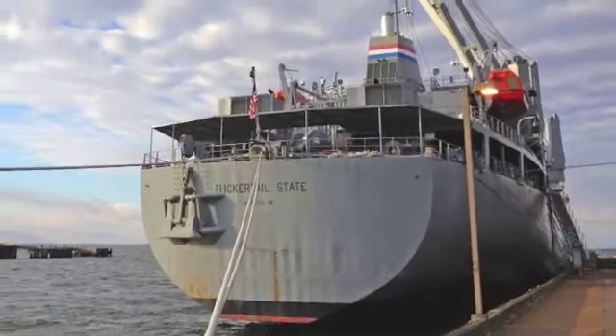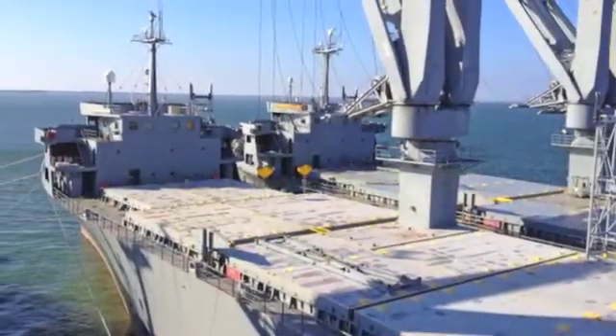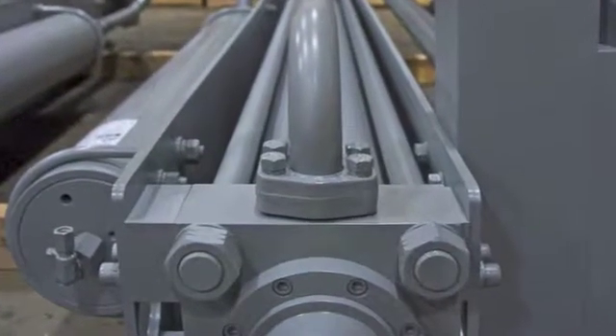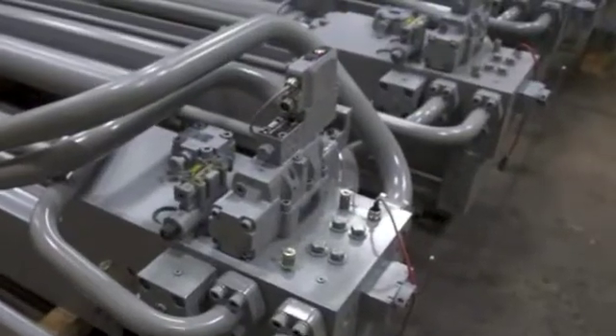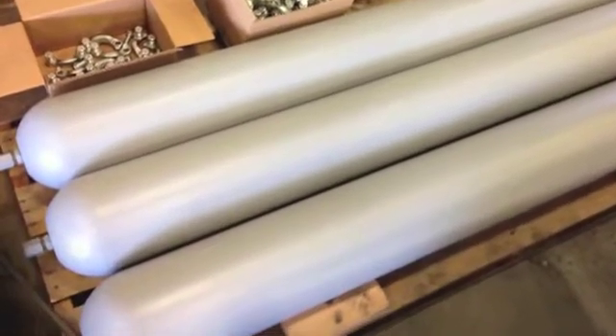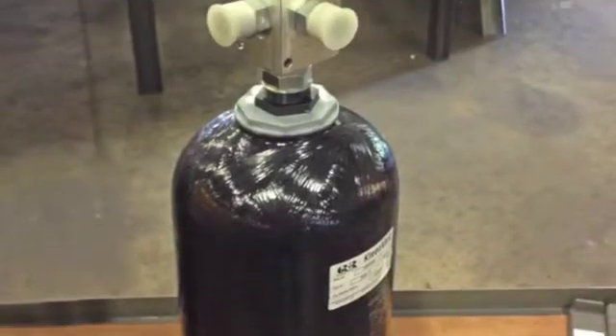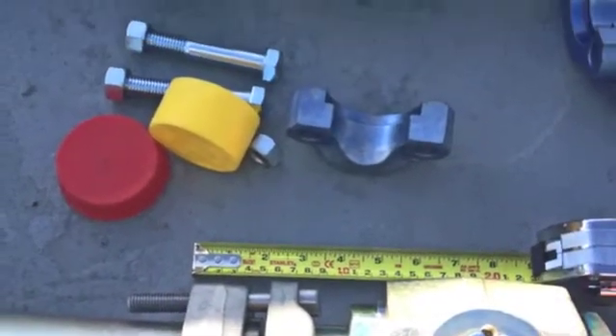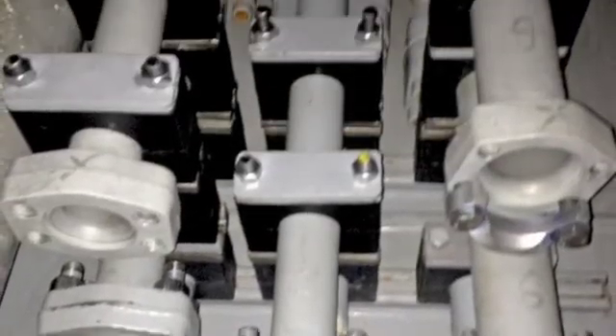Based on the first round of calculations, we determined that the system was just too large for the capacity of the ship that it was going to be placed on. So we had to do some redesign and decided to go back to a smaller size cylinder to reduce the flow requirements, thus reducing the requirements from the HPU itself. Even with doing that, it was still too large, so we determined to offset some of the horsepower requirement with stored energy accumulators. The one thing the adding of the accumulators did was add weight to the crane structure itself, which reduced the lifting capacity also. So we had to come up with a balance between all those factors to determine the actual system that we ended up with.